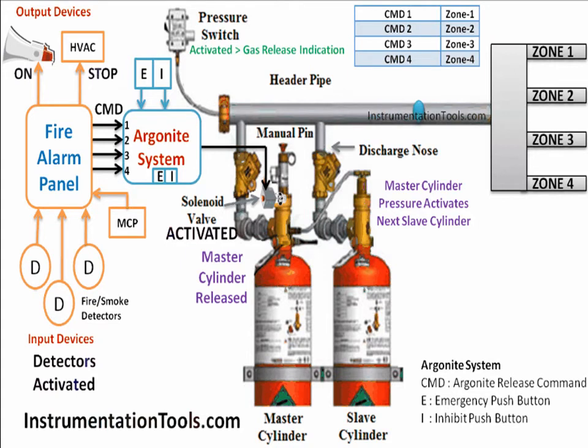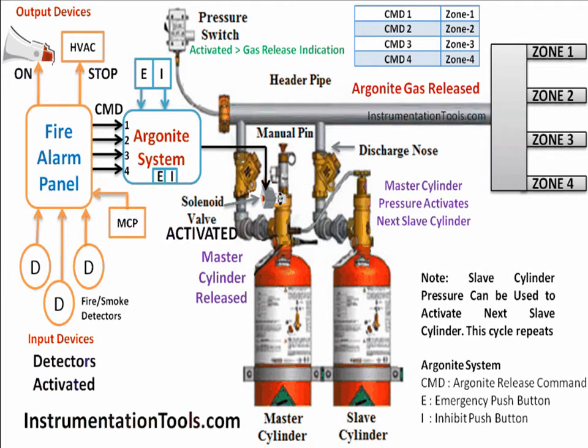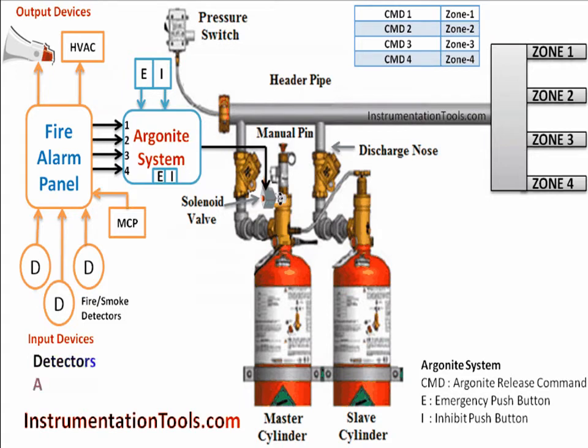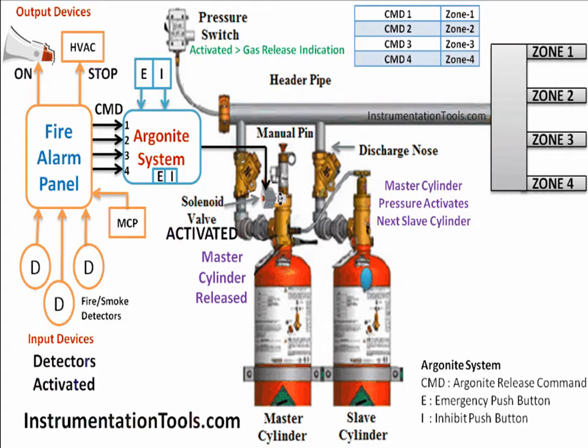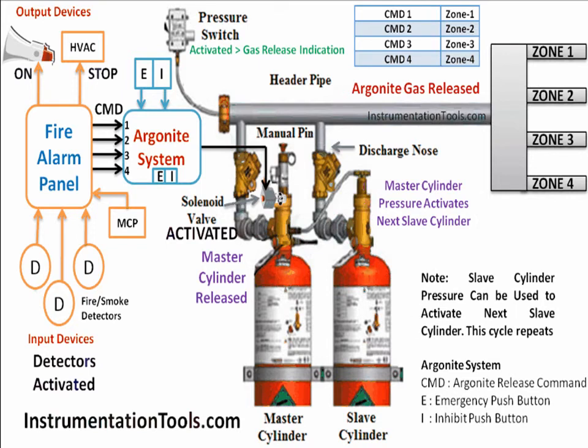In the animation, only one slave cylinder operation is shown. Using this concept, we can release many cylinders connected in series by activating one master cylinder. Since we have four zones, we release gas only to the fire-affected zone. On/off valves are provided in the zone 1, zone 2, zone 3, and zone 4 discharge pipelines. Whenever a command is received from the fire alarm panel, the respective zone valve opens immediately while remaining valves stay closed. Generally, more than one master cylinder is used either to speed up the operation or to divide cylinders among specific zones.